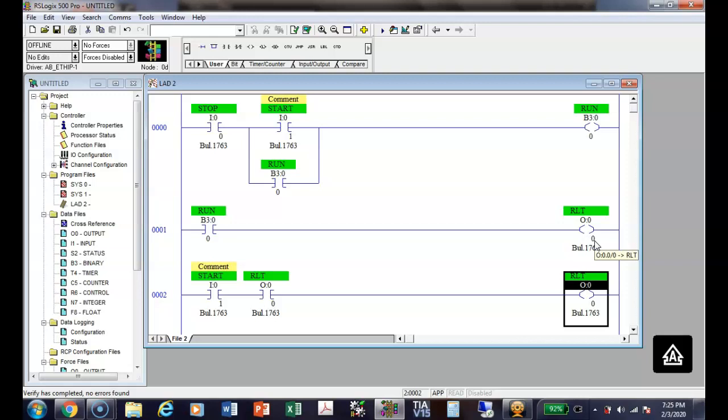So what does that mean? Well, that means if this rung is false, no matter what goes on here, this one's false. So the only way this would work if both of them is true. So what we're saying is don't do what? Don't reuse an output address. You can use the contacts of an output, but you don't need to reuse an output address. Because one thing, it don't show you you got an error, but the only way both outputs would be on if both rungs were true. And this happens in the next class more than this one. Because we're not going to be doing much of this. Notice it didn't give me a syntax error. It said it's okay.